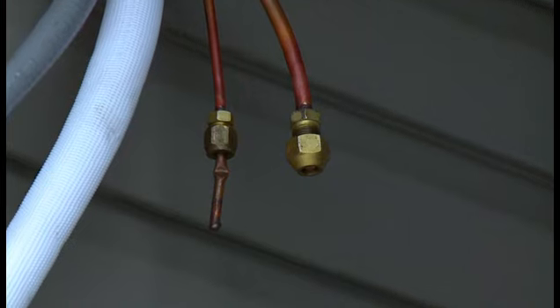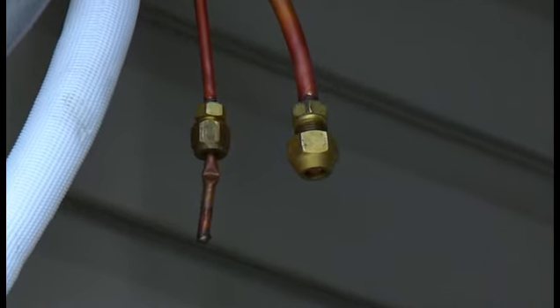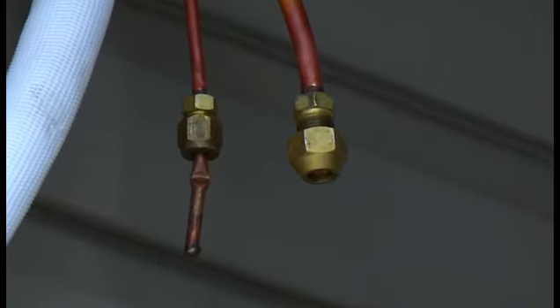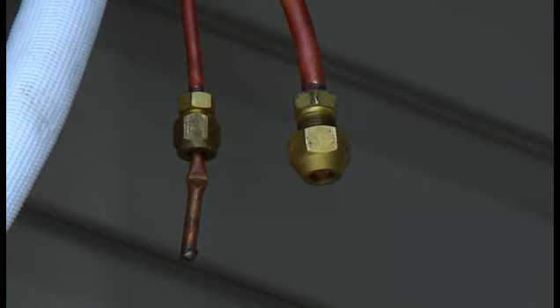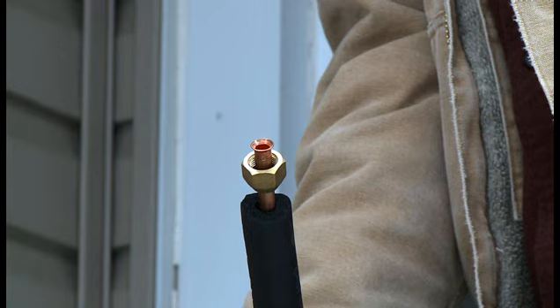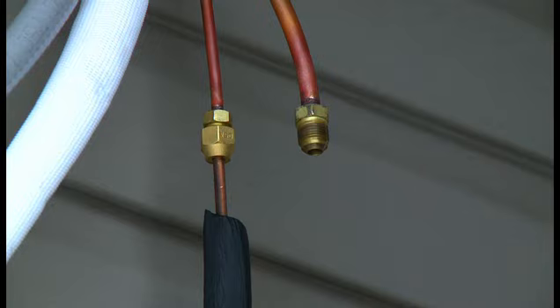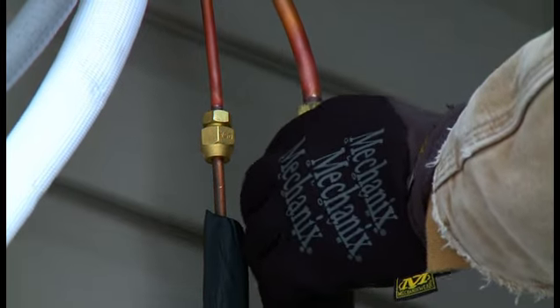Note that two sizes of lines are used to carry refrigerant to and from the interior and exterior units. The thinner of the two lines carries the liquid refrigerant to the interior unit, where the liquid becomes a gas. The larger line carries the gas to the exterior unit, to be turned back into a liquid. We will now connect the refrigerant lines. Note the lines are already flared and include the flare nuts. Connect the refrigerant tubing to the appropriate lines.